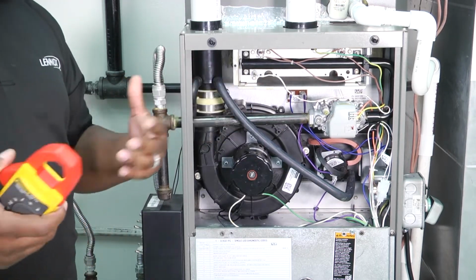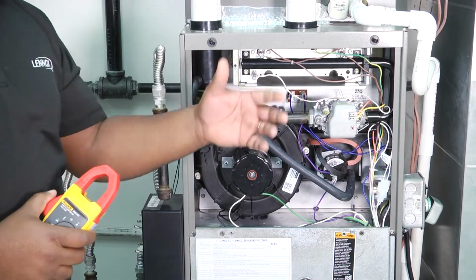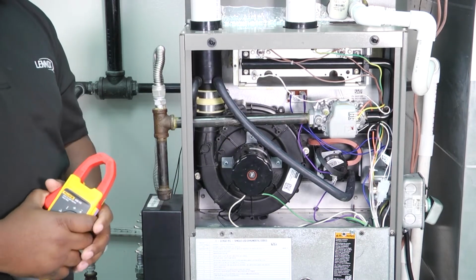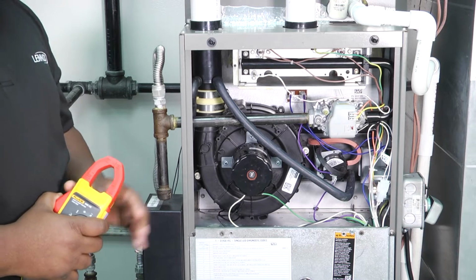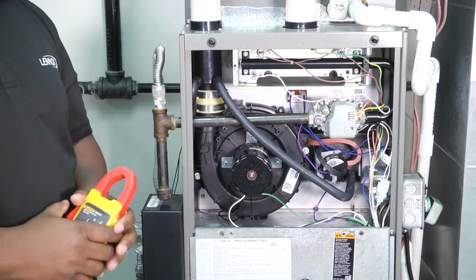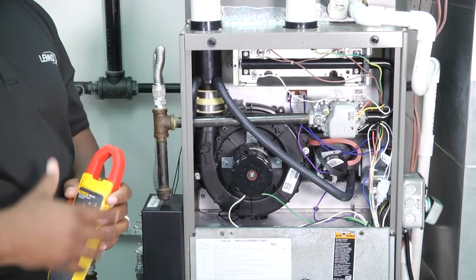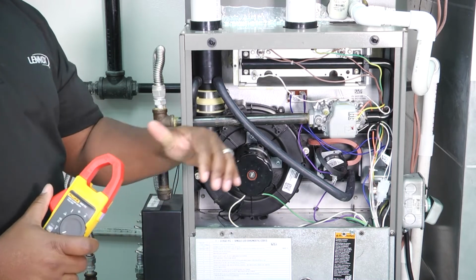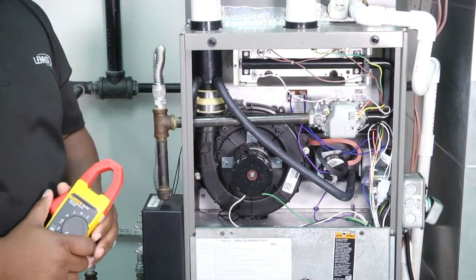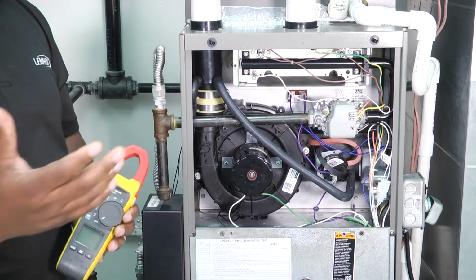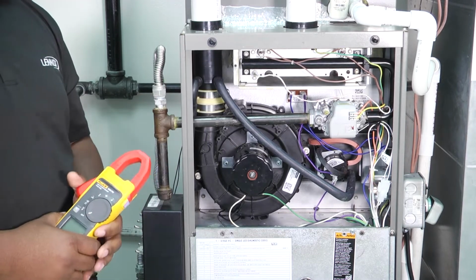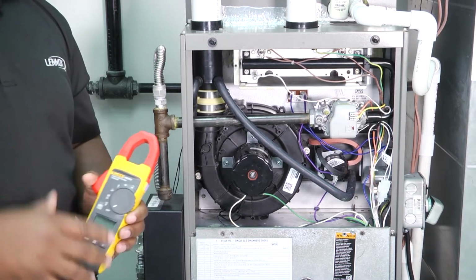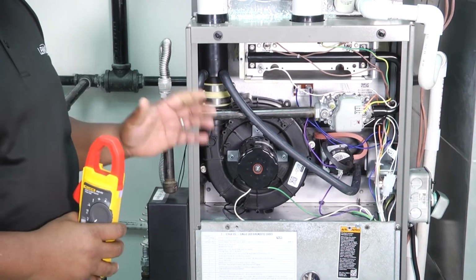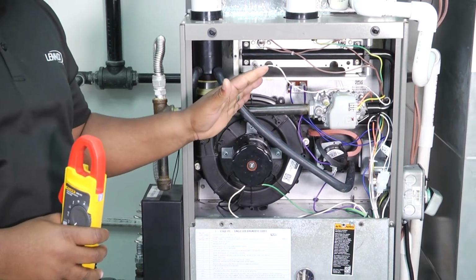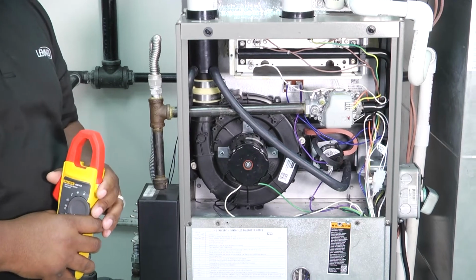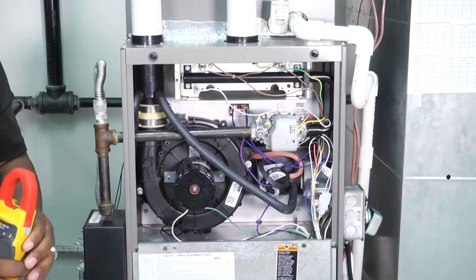Now, there's been a couple of videos out and we've seen it all. There's a lot of different things out there that you can clean and check your flame sensor with, but you want to make sure that it's clean and it tests where it needs to test. A lot of times manufacturers will say that it's above 1, which says we have a healthy flame sensor. So those numbers could range anywhere from 2.4 to 4.2 and anywhere in between. But when you check it, make sure you know what the tolerance is for the piece of equipment that you're working on, and make sure you're above that number.